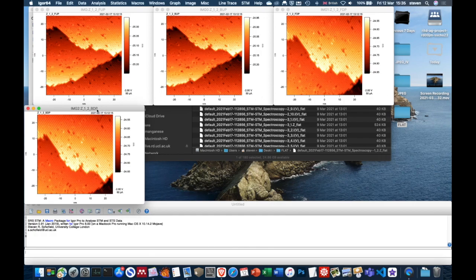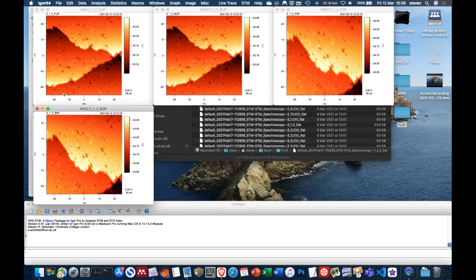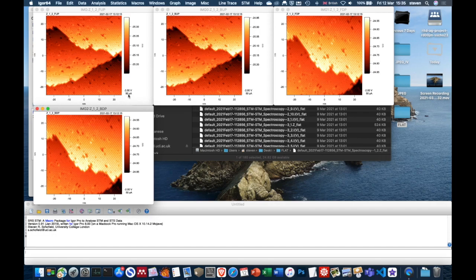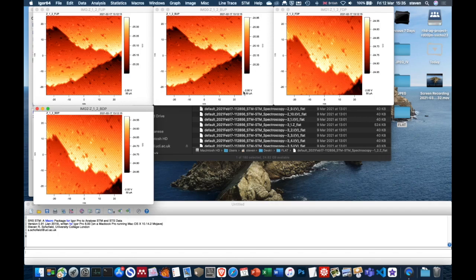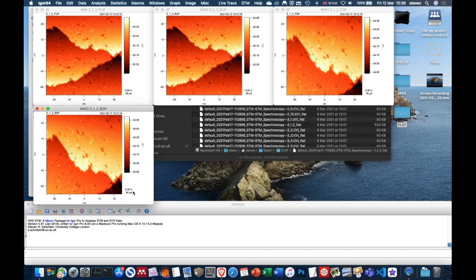The macros also tries to grab the bias and current values and put those on the images. One thing to be aware of, the way that Omicron stores the data, is it takes the image starting from the bottom, works its way up to the top. And then it takes from the top back down to the bottom. At the end it records, it saves all four images at once. And whatever the bias and current values were at the time when it reached the bottom of the down frame, that is the number that gets recorded here. So you can see these are all minus two volts and 50 picoamps. If you had minus two volts on the forward image and plus two volts on the backward image, then you would see a plus two volts here instead of a minus two volts. But if you took the whole up frame at minus two volts and then sometime during the down scan, you changed the bias to plus two volts, then all of these images would be saved with plus two volts on there. That's just something to be aware of as you're taking the data.